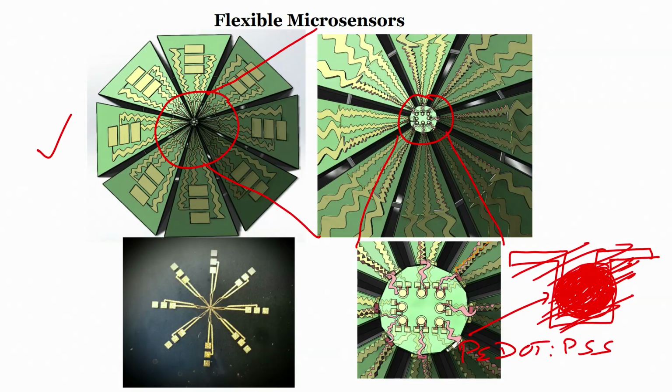Mind that there is an insulator between the strain gauge and the electrode. Now, the strain gauge has how many points? It has 2 points, 1 and 2, and the electrode has 1 point, you get it. This is what you can see in this particular image. There are 3 points going out, 1, 2, and the pink one is your third one. 2 from the strain gauge, 1 from the electrode.